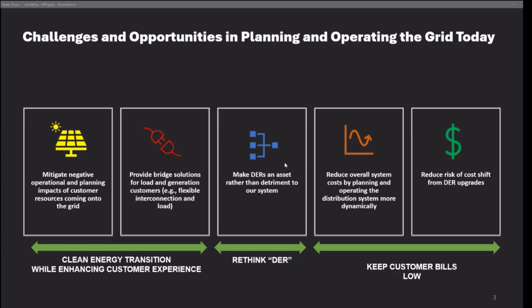Typically when customers connect, there's the concept of a cost causer—whoever hits that capacity limit has to pay for the upgrades in order to interconnect. But there are new concepts such as flexible interconnection, being presented as a solution to allow the customer to interconnect, because most of the time the constraint is during a very isolated period of the year, maybe a few percent of the year. So if we can avoid those constrained times, we can allow the customer to interconnect, but the customer has to agree to be curtailed or have limited generation, which requires new interconnection agreements.